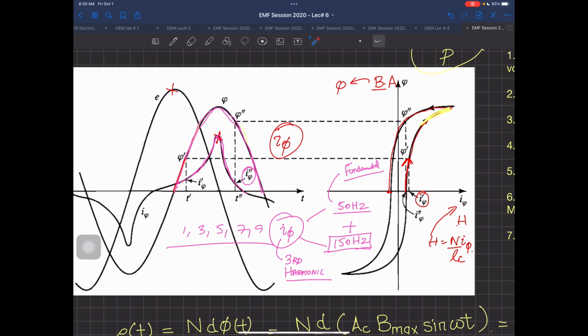So what we do is our source remains 50 Hertz. WAPDA is supplying us the 50 Hertz waveform, but due to saturation of our core, it takes a current waveform like this, and because of this current waveform, it has harmonics inside it, meaning it has a 3rd harmonic, 5th harmonic, 7th harmonic, 9th harmonic, and so on. It can even go up till the 49th harmonic in some cases, if the machine device is bad.